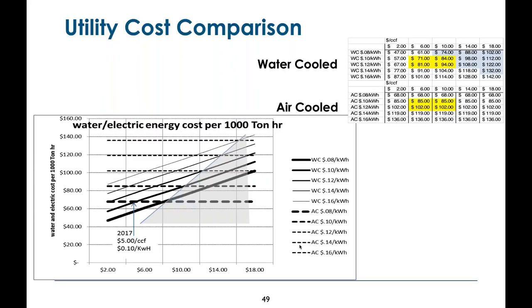Another interesting trend is if you look at the ratio of water cost to electric energy cost in a chiller plant. This graph gives you an idea of what those costs are for a 1,000-ton plant. Certainly the air-cooled plant doesn't care, it's independent of water, but for a water-cooled plant, the higher the water cost, the more overall cost that's going to induce.